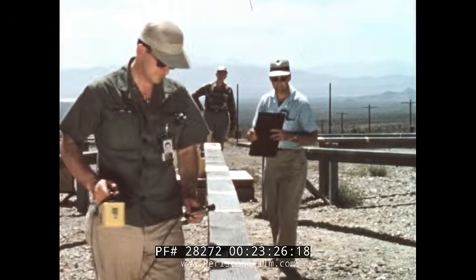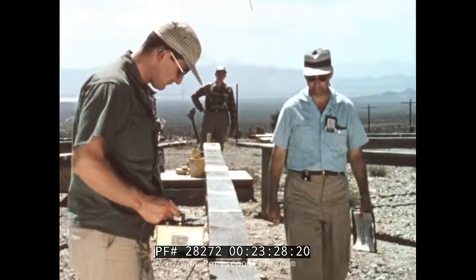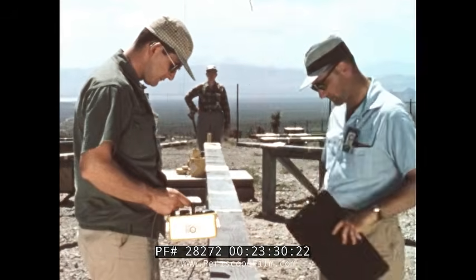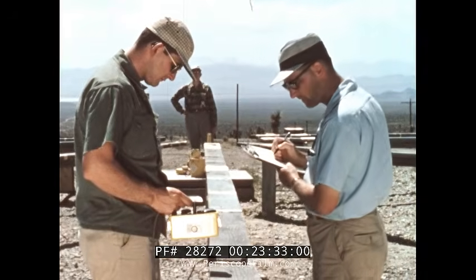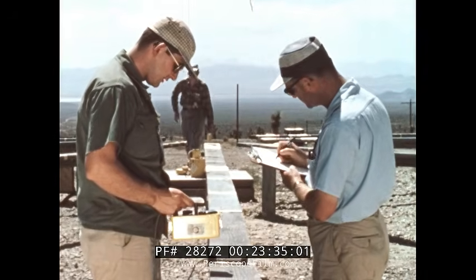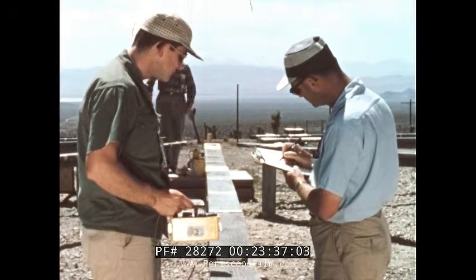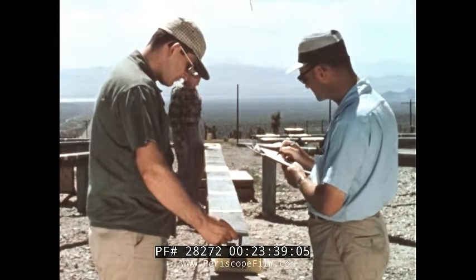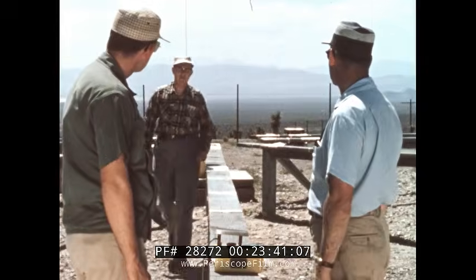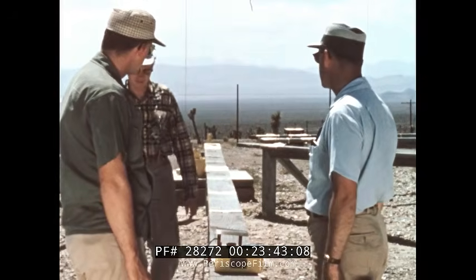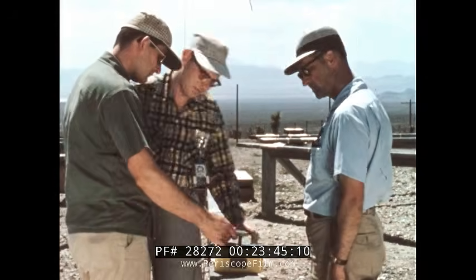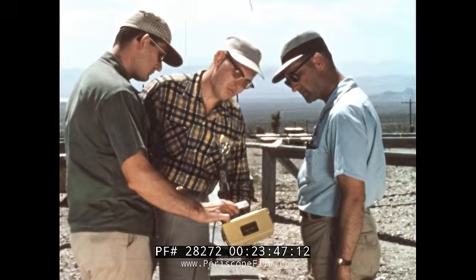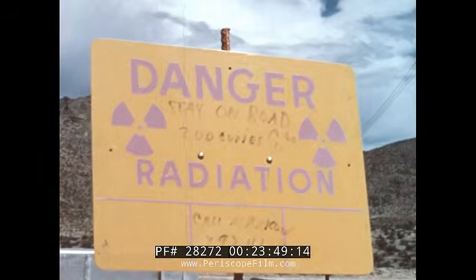The monitors then take readings at all points on the range. At each subsequent point, the reading is noted and logged. No further adjustment of the calibration screw is made, since the results for each instrument will be graphed and maintained as the meter's characteristics.